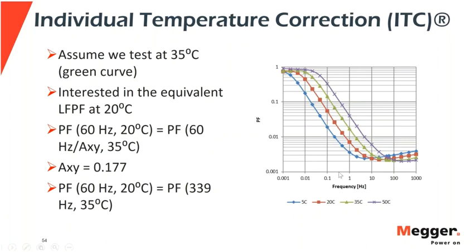So here are the curves from the dryer transformer. Again, it's 35 to 20, with that same frequency shift factor. I want to determine what happens if I let my transformer cool from 35 to 20, and you can see that they're practically the same.